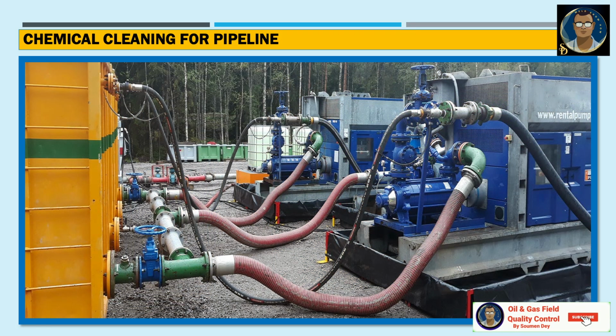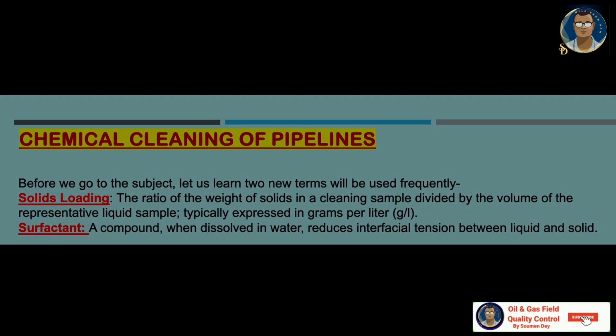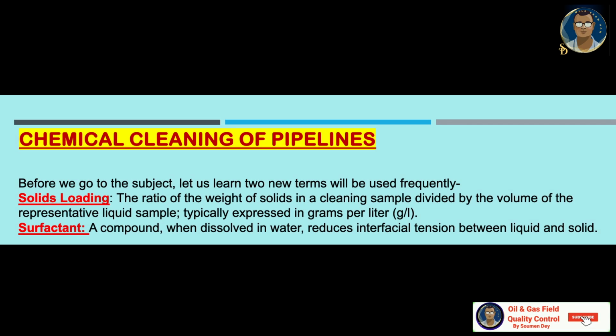Let us go a little bit in detail for chemical cleaning of pipelines. Before we go to the subject, let us learn two new terms which will be used frequently. In the acceptance standards of chemical cleaning I discussed before, you heard a term, solids loading. What is that? The ratio of weight of solid in a cleaning sample divided by the volume of the representative liquid sample, typically expressed in gram per liter. We read the acceptance standard was 5 gram per liter. Surfactant: it is a compound that, when dissolved in water, reduces interfacial tension between liquid and solid.